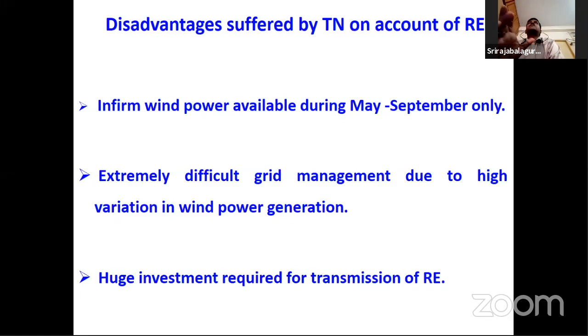So if you see 2000 megawatt or 3000 megawatt at this time, and suddenly it is not there, the megawatt is reduced by, say for example, some 100 megawatt. So grid management is difficult. We have different sources of power: thermal, gas turbine, which is called a spinning reserve, thermal power station, and hydropower. So we will manage the grid with the help of the spinning reserve, so even if we have disadvantages in wind power, they will be managed by the spinning reserve.